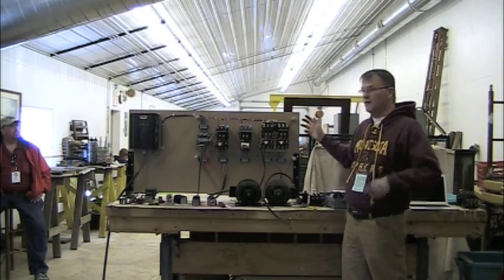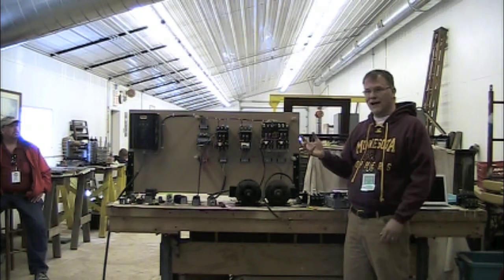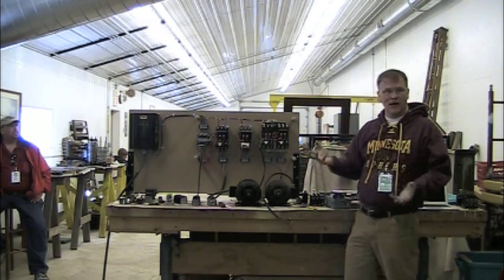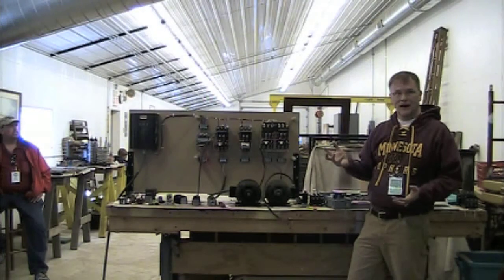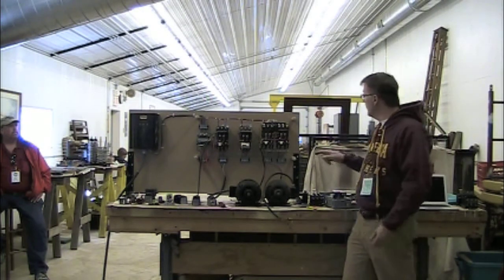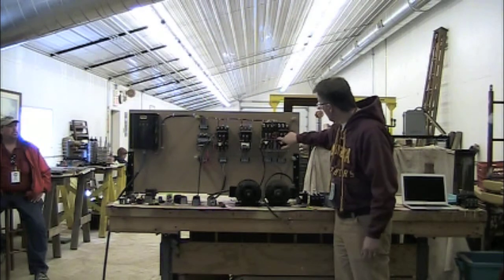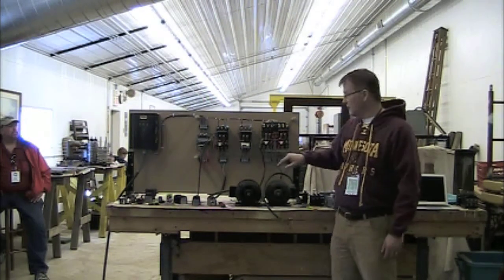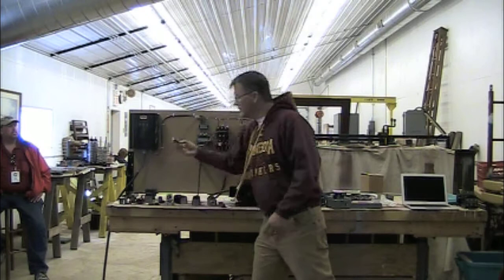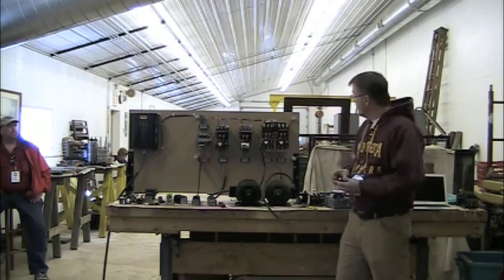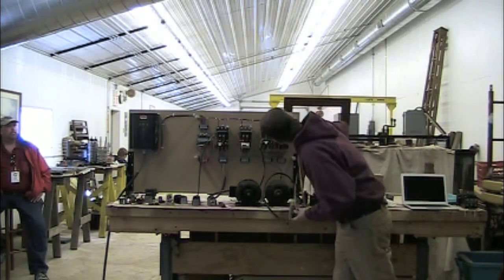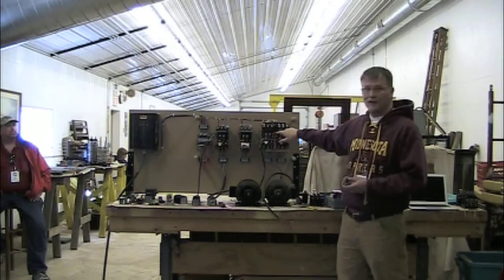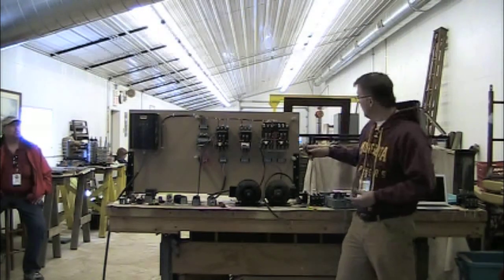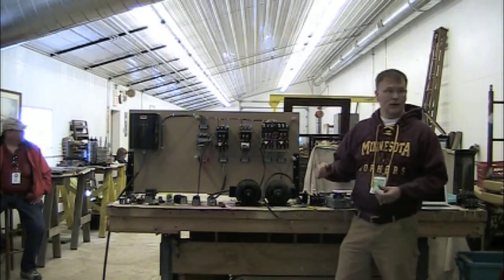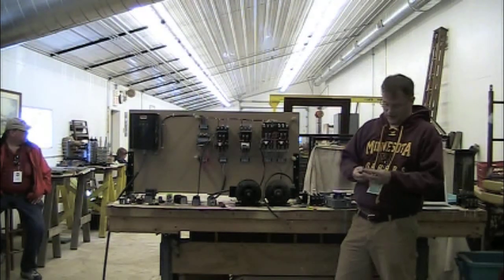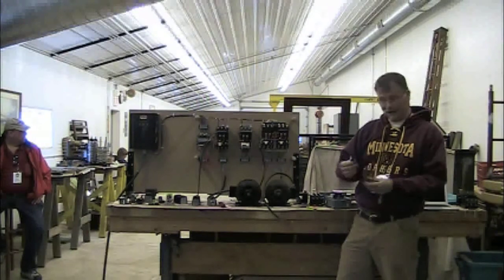You need a lot more control circuit logic to be able to manage the two speeds, the two contactors independently. So there's a bunch of extra of those auxiliary contact blocks, these right here. There's 2 of them on here, and these are a double-decker one that has a normally open and a normally closed. These are Bulletin 595.